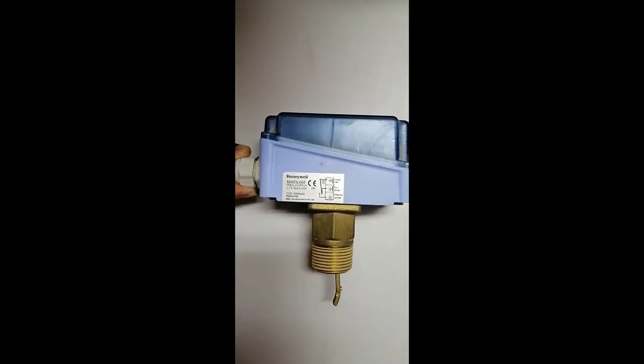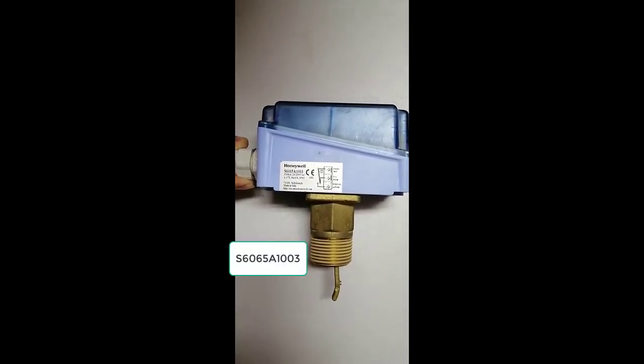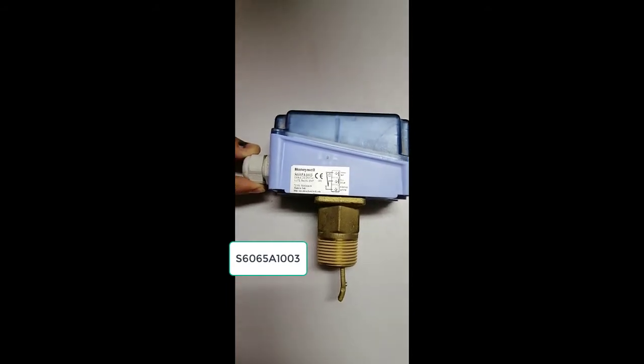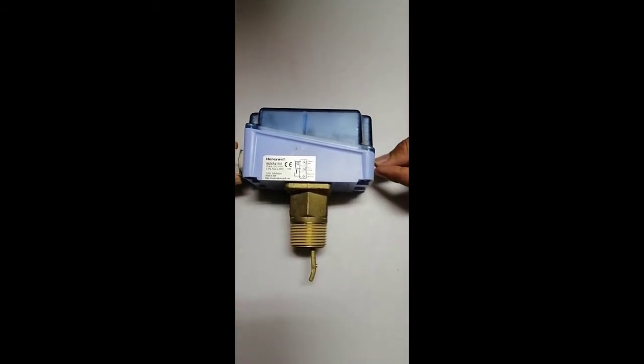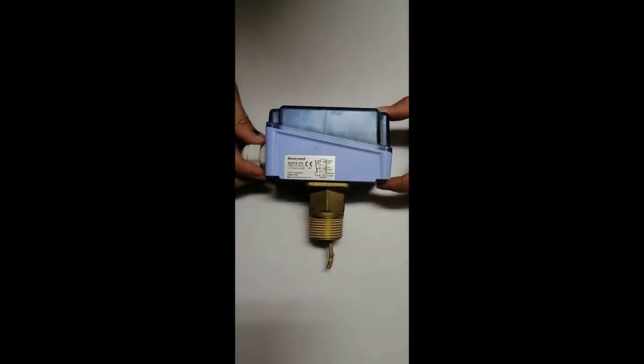This is a water flow switch. The part number from Honeywell is S6065A1003. We install this in chiller plants to detect the flow through the chiller. When we detect the flow, then after that we enable the chiller. So it is also a switch. It provides us dry contact. Let me open this one to show you the contacts.